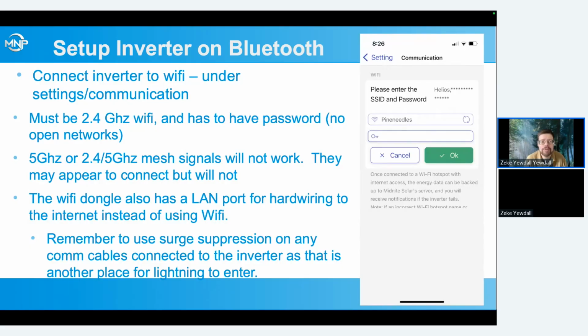We want to go through and connect it to Wi-Fi now. This is under settings and communication. Couple tricks here. It has to be a 2.4 gigahertz Wi-Fi and it has to have a password. It won't connect to open networks and it won't connect to a lot of the kind of 2.4 or 5 gigahertz mesh signals that some of the newer routers put out. I've heard that the new Starlinks do that and you can't turn off the 5 gigahertz side. So in that case, you may need to look at hardwiring it or doing some sort of Wi-Fi adapter rather than connecting it directly.